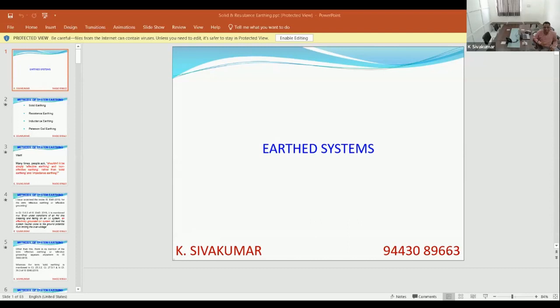Yes, all currents will be there. But in the zero sequence network, there is no sequence at all. The very term zero sequence means there is no phase sequence at all. It does not follow any sequence. So in zero sequence, all the vectors will add arithmetically. There is no negative sequence, there is no positive sequence. In zero sequence, all the currents add arithmetically, not vectorially.